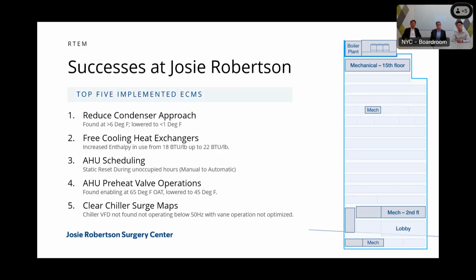Another project we did was maximize the use of our economizers. So instead of just using one, we used both our economizers, slowed down our chill water flow, and got the most out of our heat rejection. We were able to maintain free cooling without any mechanical cooling up to 22 BTUs of enthalpy, which is quite significant in my opinion.